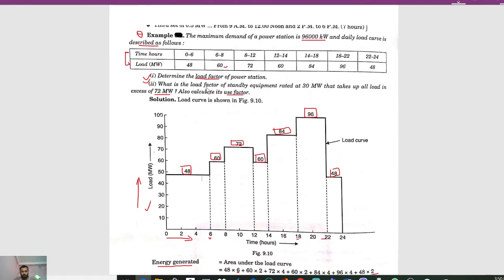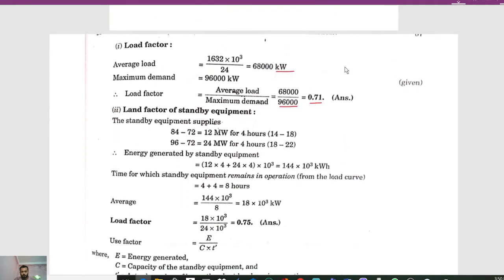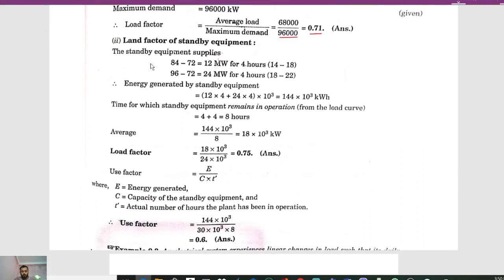Now for the load factor of the standby equipment rated at 30 megawatt that takes up all load in excess of 72 megawatt. Above 72 megawatt we have 84 and 96. So 84 − 72 = 12 megawatt for 4 hours (14 to 18), and 96 − 72 = 24 megawatt for 4 hours (18 to 22).